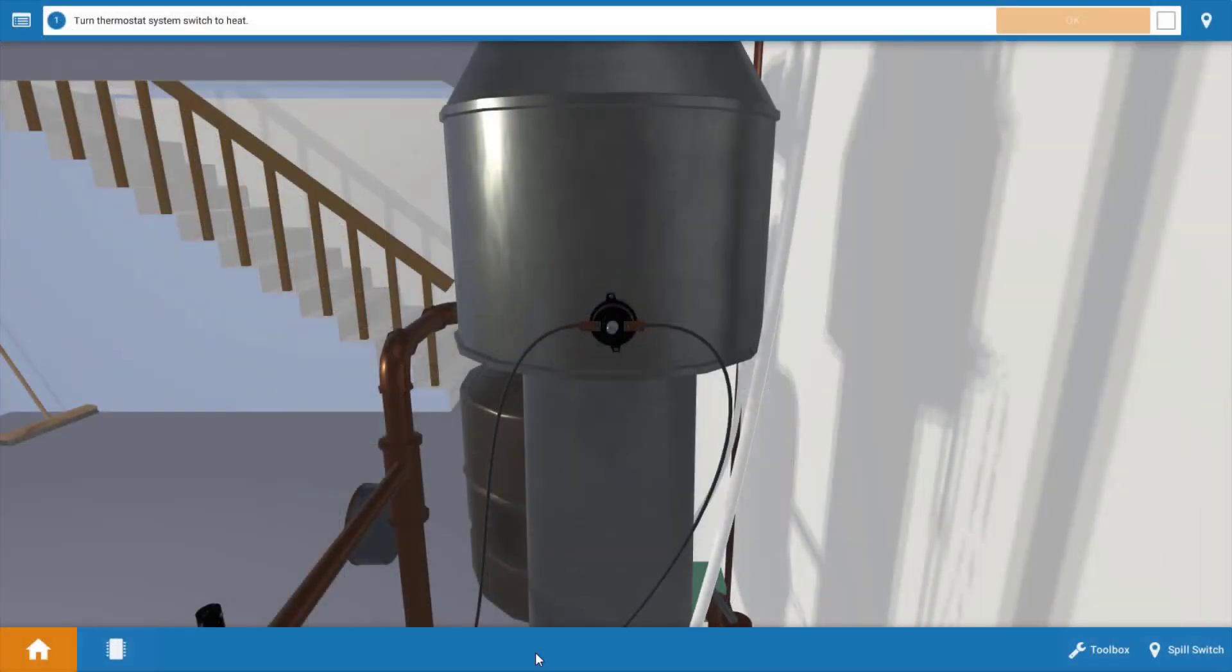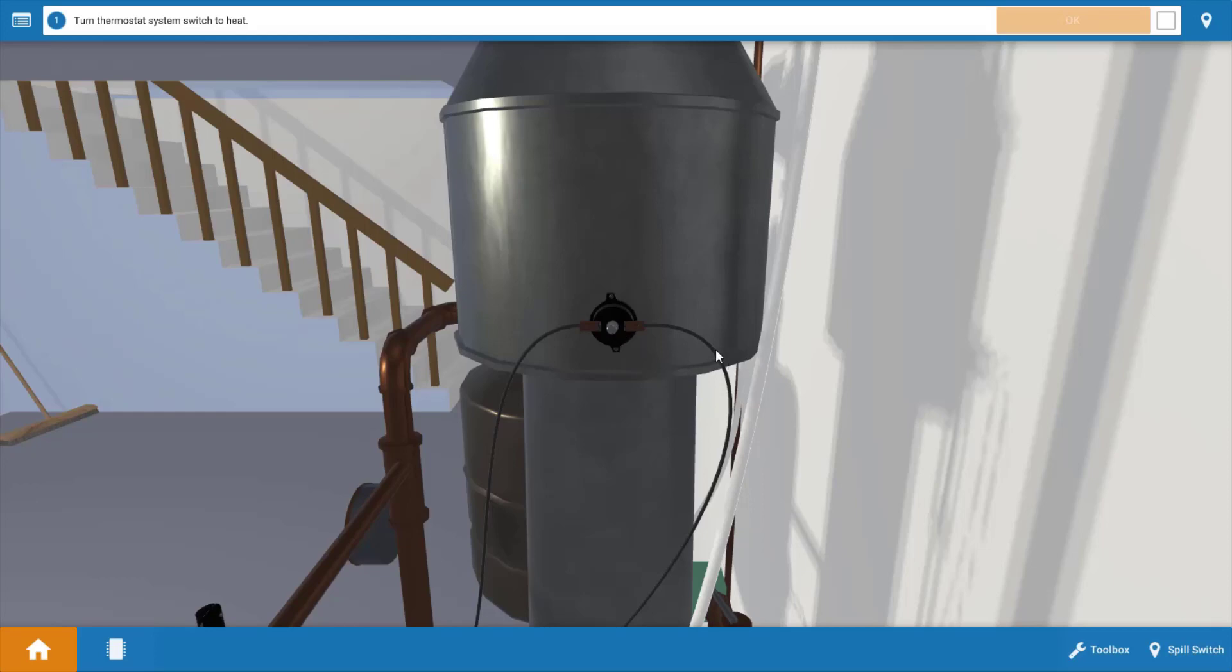Now first let's take a look at the spill switch. It's right here in the center and it's located within the draft hood or draft diverter of an atmospheric gas appliance. Its function is to protect against spillage or backdrafting of combustion gases out of the draft hood and into the living space. This would occur in the event that you had an obstruction in the chimney, poor vent design, or possibly a competing exhaust appliance nearby that's pulling these gases out into the space.